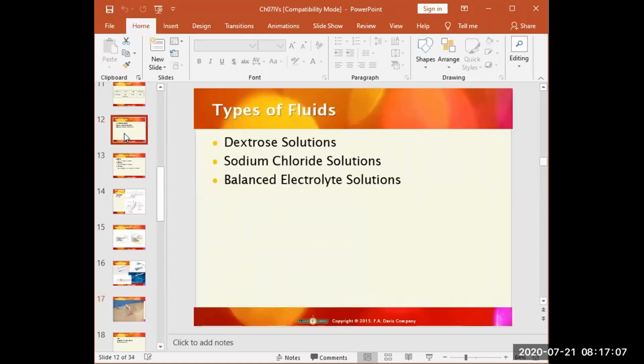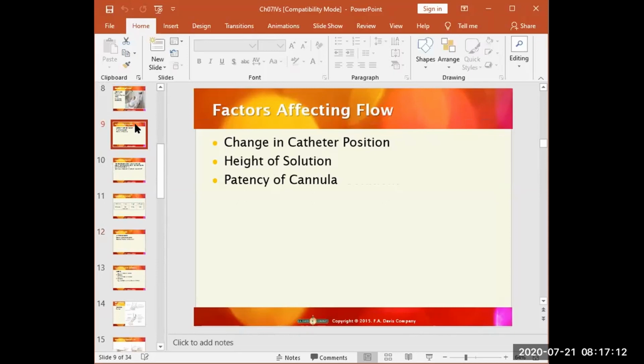Okay, so back to the things that affect it. The height of the solution. Because infusions flow by gravity, a change in the height of the infusion bag or bottle, or a change in the level of the bed, can increase or decrease the flow rate. The flow rate increases as the distance between the solution and the patient increases. They really mean the height. A patient may inadvertently alter the flow rate greatly by simply standing up. The ideal height for a solution is 3 feet above the level of the patient's heart. So that's going to be important to remember.